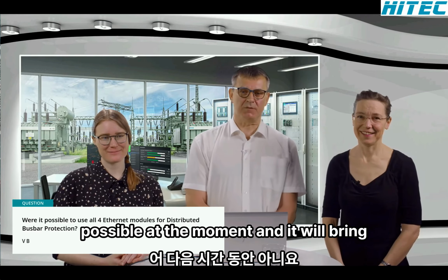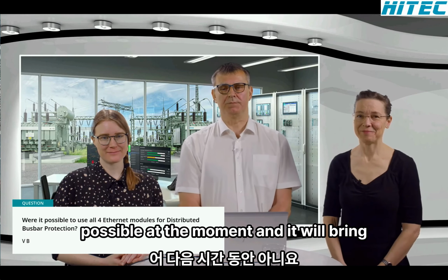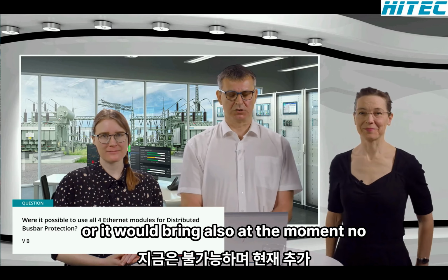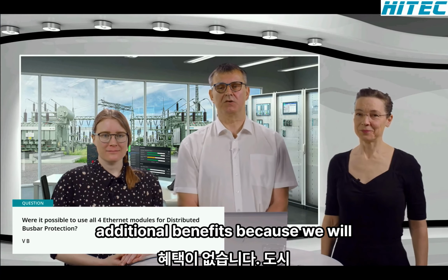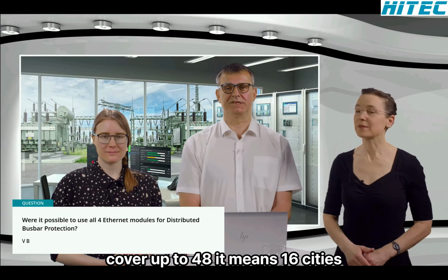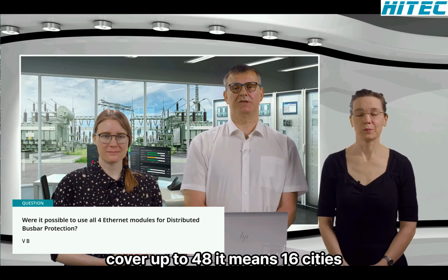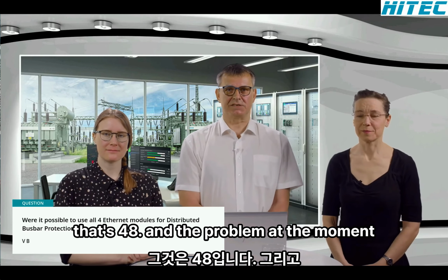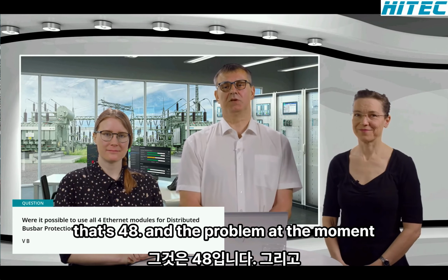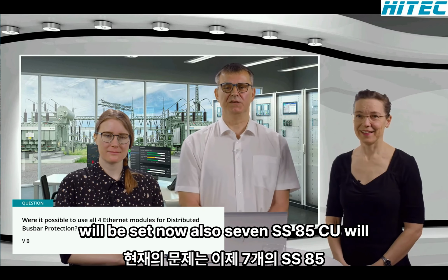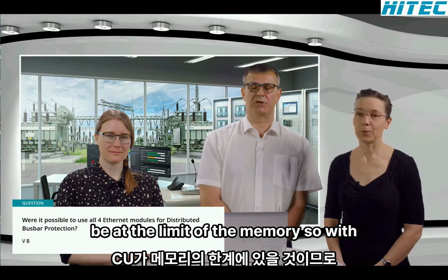No, it's not possible at the moment, and it would bring also at the moment no additional benefits, because we will cover up to 48. That means 16 CTs per Ethernet BT module. That's 48. And the problem at the moment will be that now also the 7SS85CU will be at the limit of the memory.